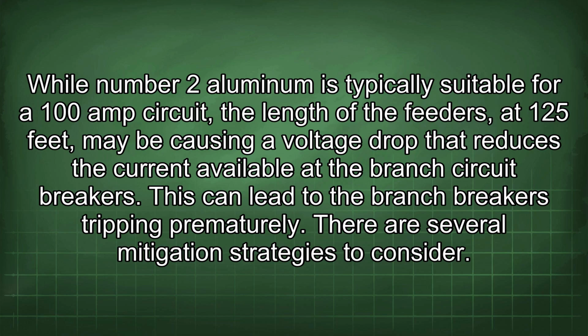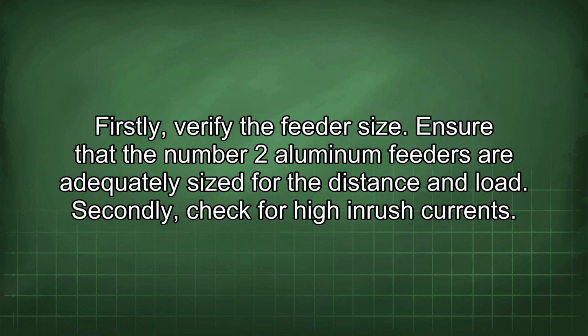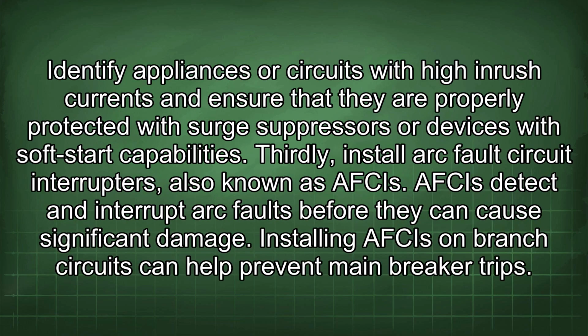There are several mitigation strategies to consider. Firstly, verify the feeder size. Ensure that the number 2 aluminum feeders are adequately sized for the distance and load. Secondly, check for high inrush currents.